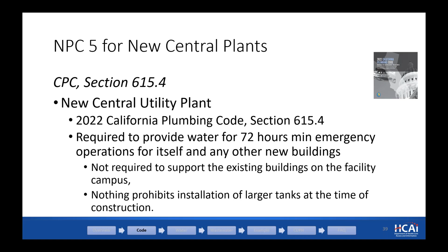As always, the fun stuff is in the exceptions or footnotes. So there are exceptions under California Plumbing Code Section 615.4, which allows smaller tanks where alternate arrangements have been made for delivery of water. What this exception is doing is allowing us to reduce the on-site water requirement from 72 hours to 24 hours, as long as alternate arrangements are made for the remaining time.